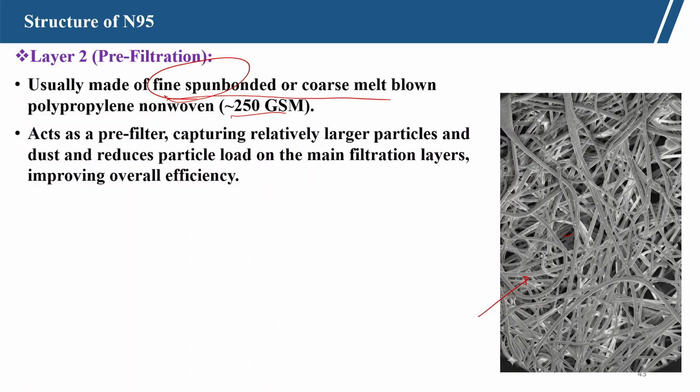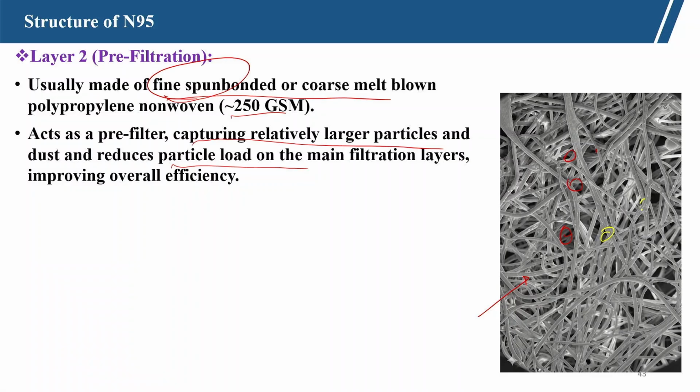It acts as a pre-filter, capturing relatively large particles and dust, and reduces the particle load on the main filter. So, it prevents the larger particles from going and loading the main filter layer.